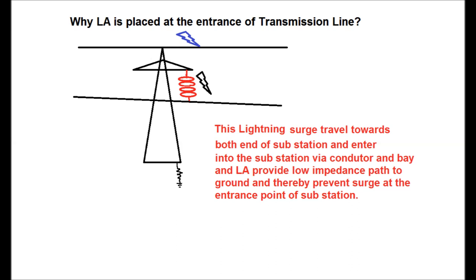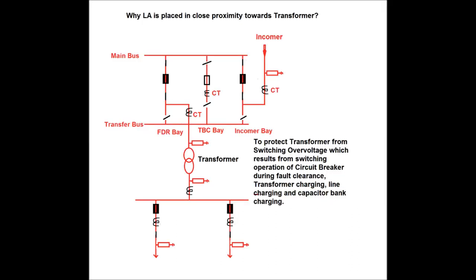Why is LA placed in close proximity to the transformer? LA is placed on the HV side and LV side in very close proximity to the transformer in order to protect the transformer windings — HV side winding and LV side winding — from switching overvoltage resulting from switching operations of the circuit breaker during fault clearance, transformer charging, line charging, and capacitor bank charging. This LA provides a low impedance path during switching overvoltage, thereby protecting the transformer, which is the most costly equipment in the substation.